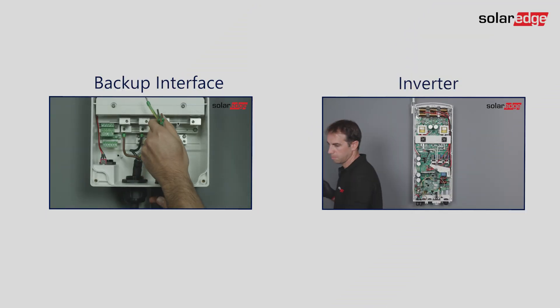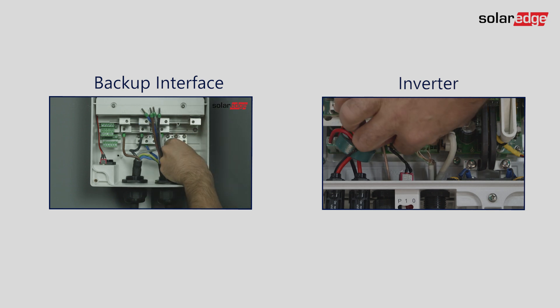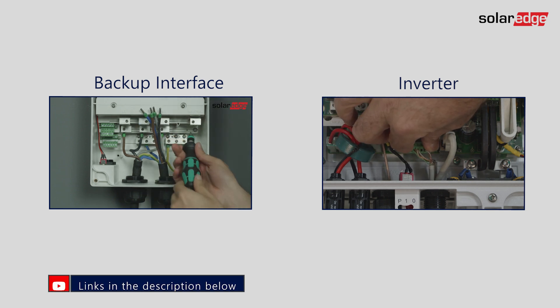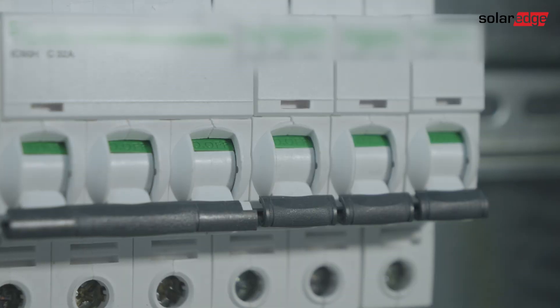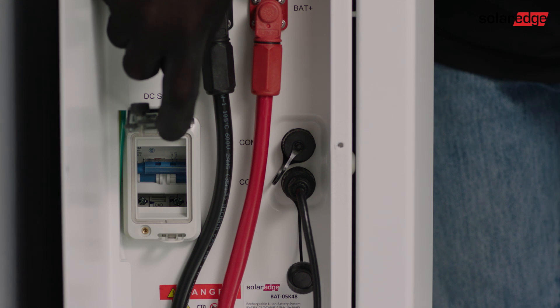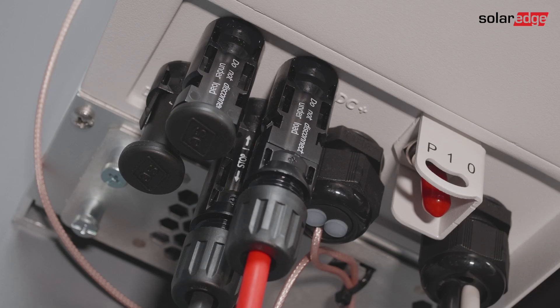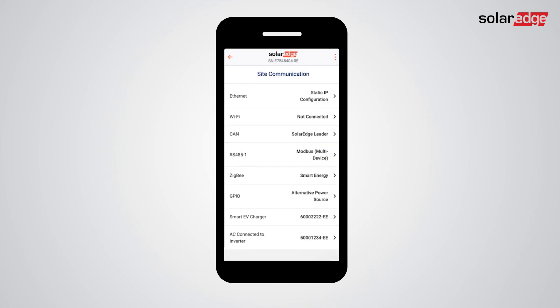Connect the BUI to the inverter and make the electrical connections to the BUI and inverter as described in the connection manuals and videos — you can find them in the description of this video. Please make sure all system components are switched on. Now set the inverter's P10 switch to 1. Set the meter as export/import and its ID to number 3.